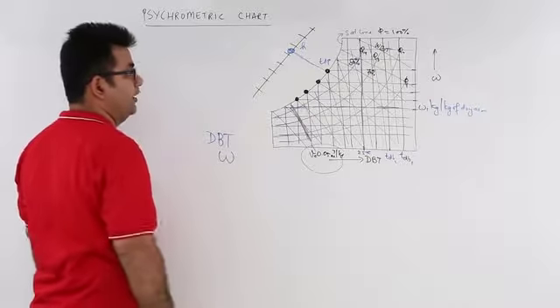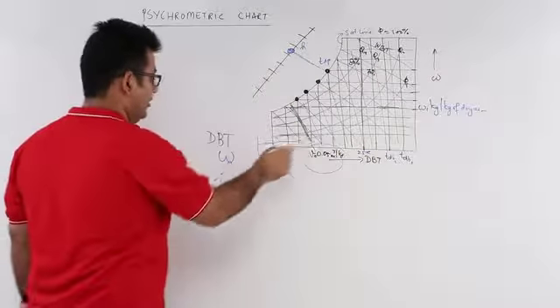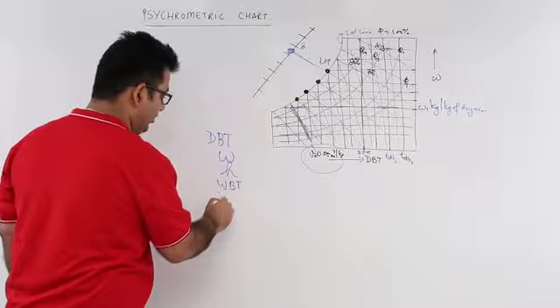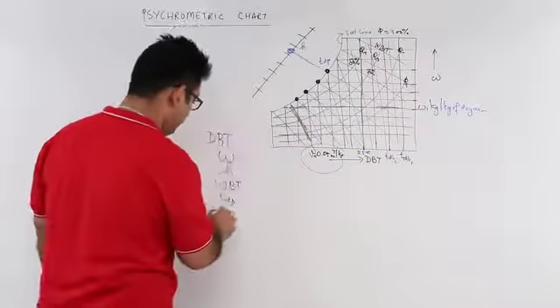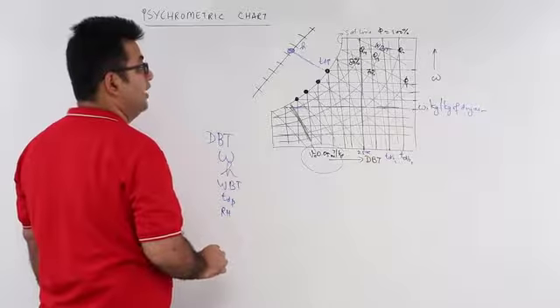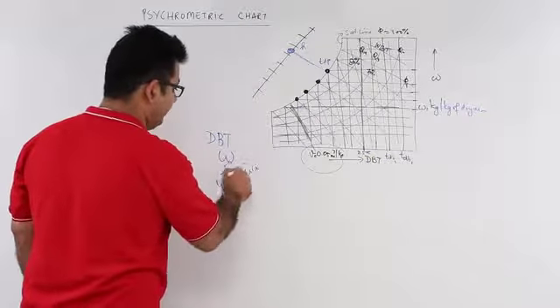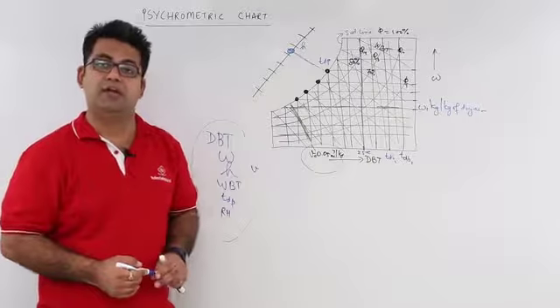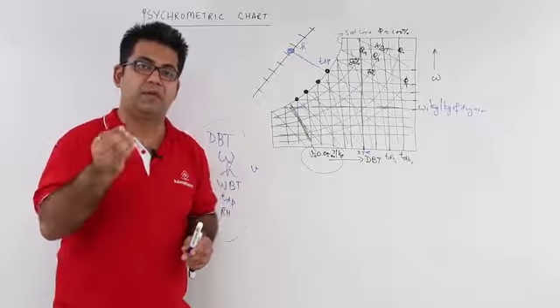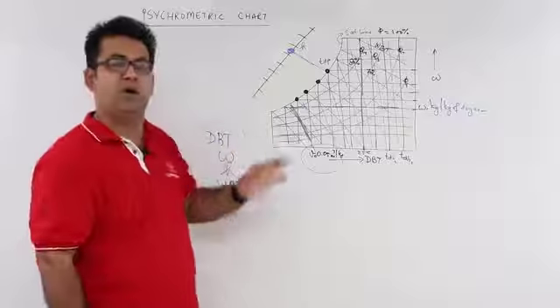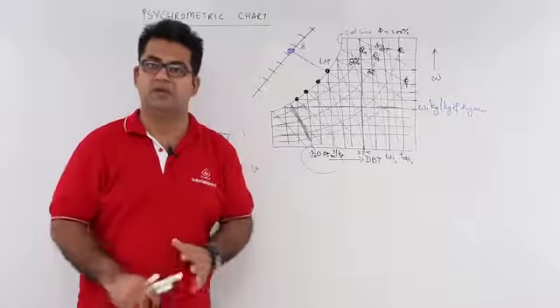In a nutshell, the psychrometric chart gives you: dry bulb temperature on the horizontal axis, specific humidity (omega) on the vertical axis, enthalpy on the enthalpy axis, wet bulb temperature from the slant lines, dew point temperature, relative humidity, and specific volume. All psychrometric terms can be found through this chart — you do not need to remember separate psychrometric relations if you know how to use it.